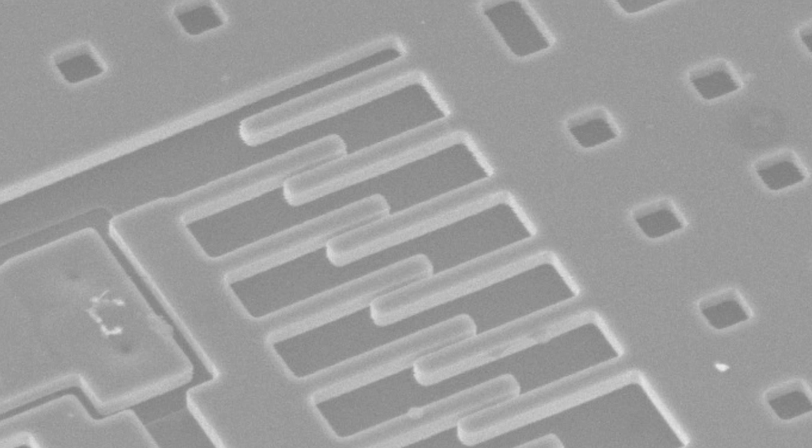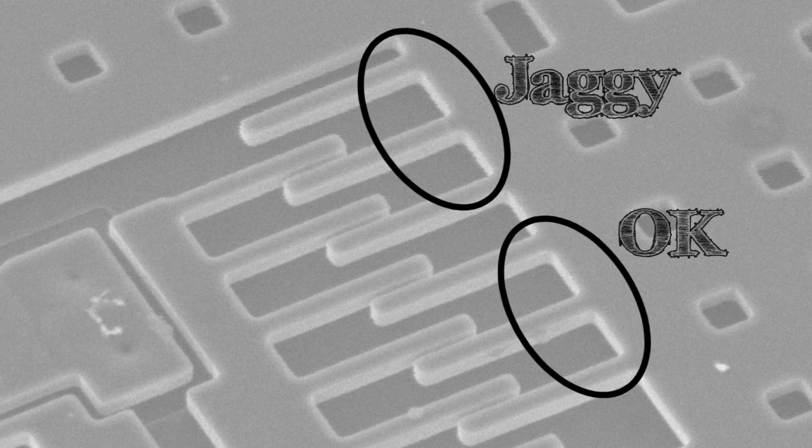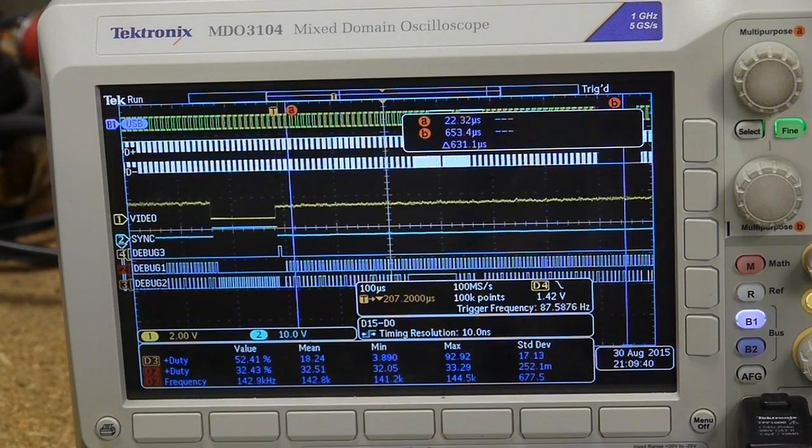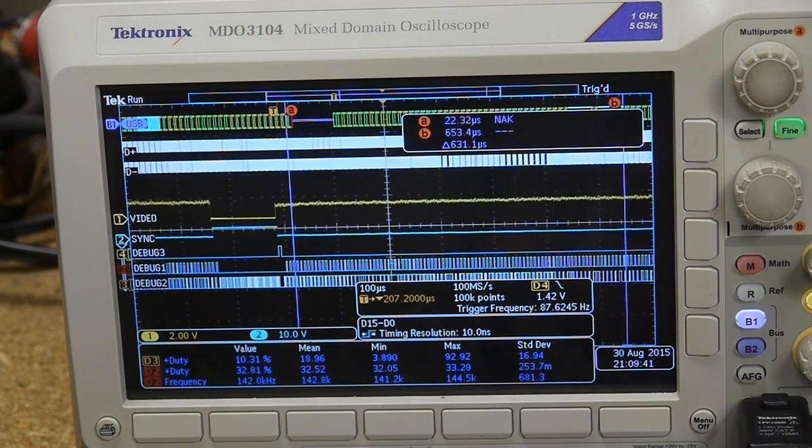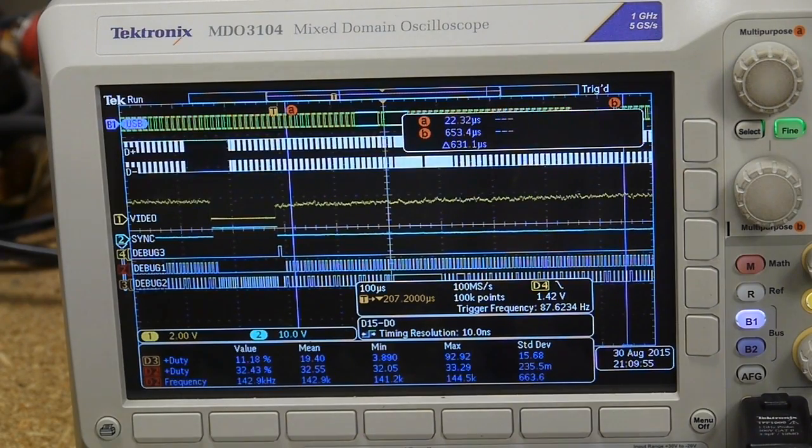Let me show you what happens if we don't have good sync up. This is an image that shows this jaggies problem—the image is sort of jagged up there. The reason is that on some lines, the ADC would be restarted a few pixels too early or too late. It's kind of a small image problem, but I got to the point where I realized I could fix it, and so then I had to. Syncing up or stopping the ADC and then starting it at the end of the sync pulse solved the problem very well.